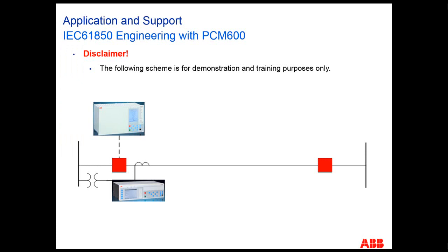The following video will show you how to engineer IEC 61850 with PCM600. To do that, we have a protection scheme which is for demonstration and training purposes only. On this protection scheme, there is an REL650 relay which is in charge of protecting this transmission line, and an REC670 relay which will be publishing the circuit breaker position.